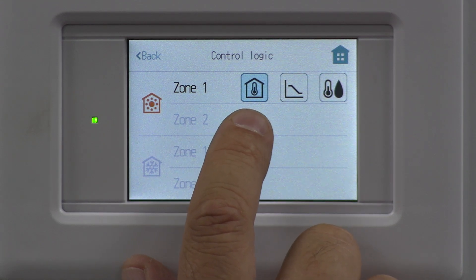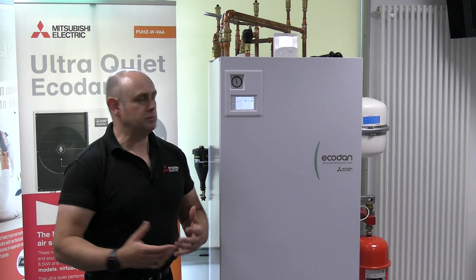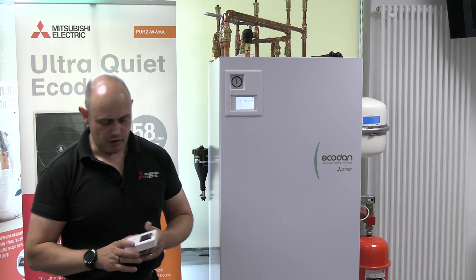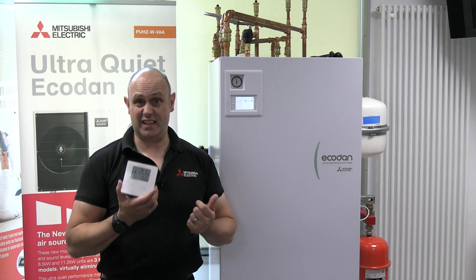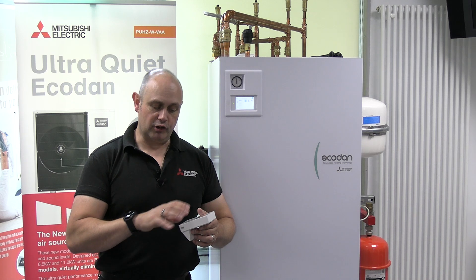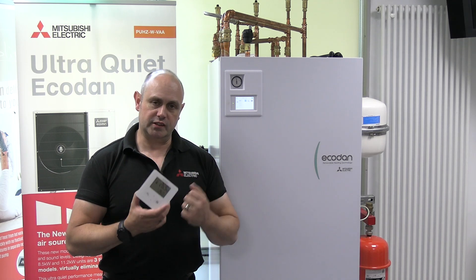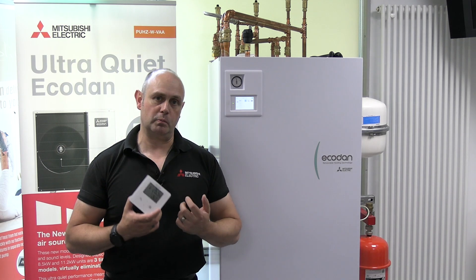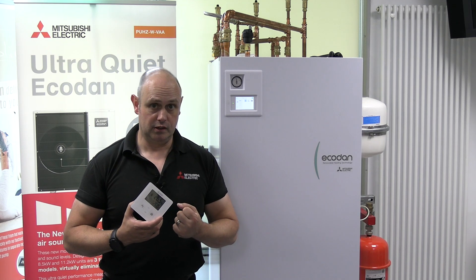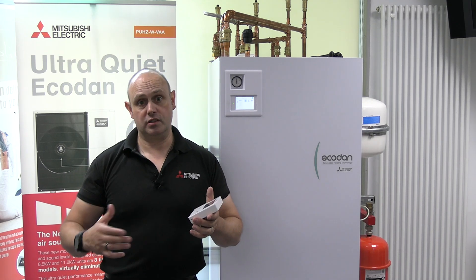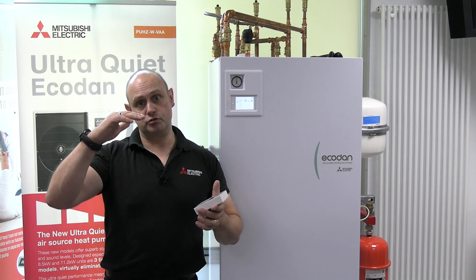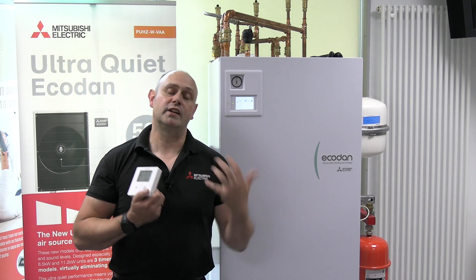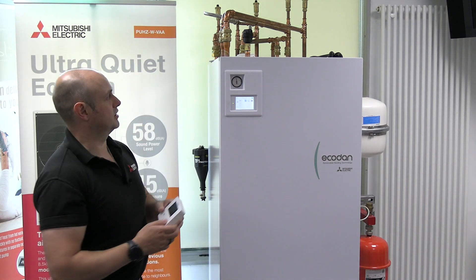The first mode is 'auto adaption'. I can use either the main controller or, in this situation, I've set up a wireless controller that I can put somewhere sensible to change the room temperature. Auto adaption looks at the room temperature you're trying to achieve, what the current room temperature is, and it tweaks the weather compensation curve in the background. As the outside temperature increases, it reduces the flow temperature. This is a self-learning system, so this is the most efficient way to run a system — for something like radiators. That's the important bit.